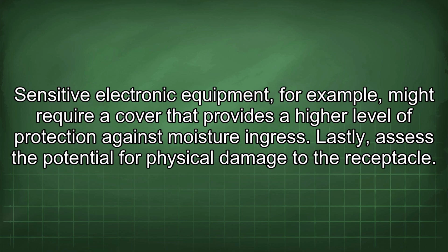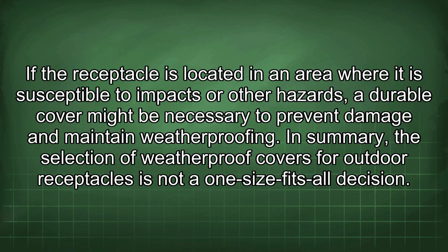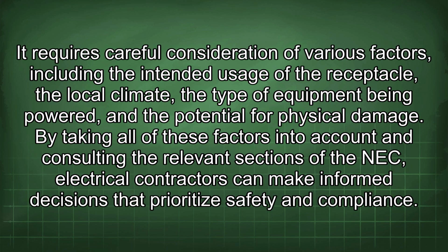Sensitive electronic equipment, for example, might require a cover that provides a higher level of protection against moisture ingress. Lastly, assess the potential for physical damage to the receptacle. If the receptacle is located in an area where it is susceptible to impacts or other hazards, a durable cover might be necessary to prevent damage and maintain weatherproofing. In summary, the selection of weatherproof covers for outdoor receptacles is not a one-size-fits-all decision. It requires careful consideration of various factors, including the intended usage of the receptacle, the local climate, the type of equipment being powered, and the potential for physical damage. By taking all of these factors into account and consulting the relevant sections of the NEC, electrical contractors can make informed decisions that prioritize safety and compliance.